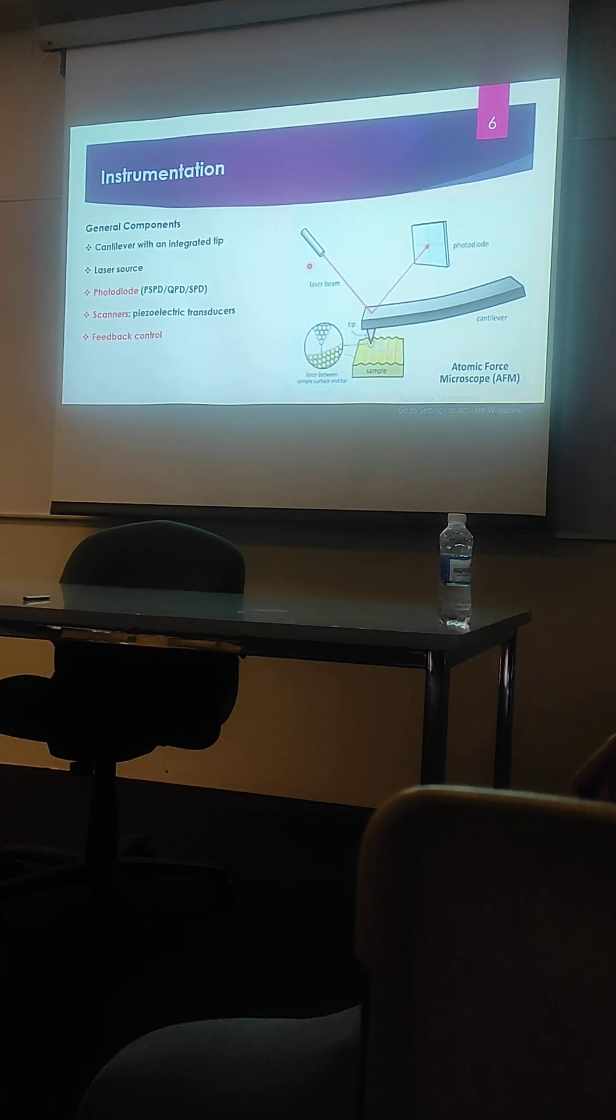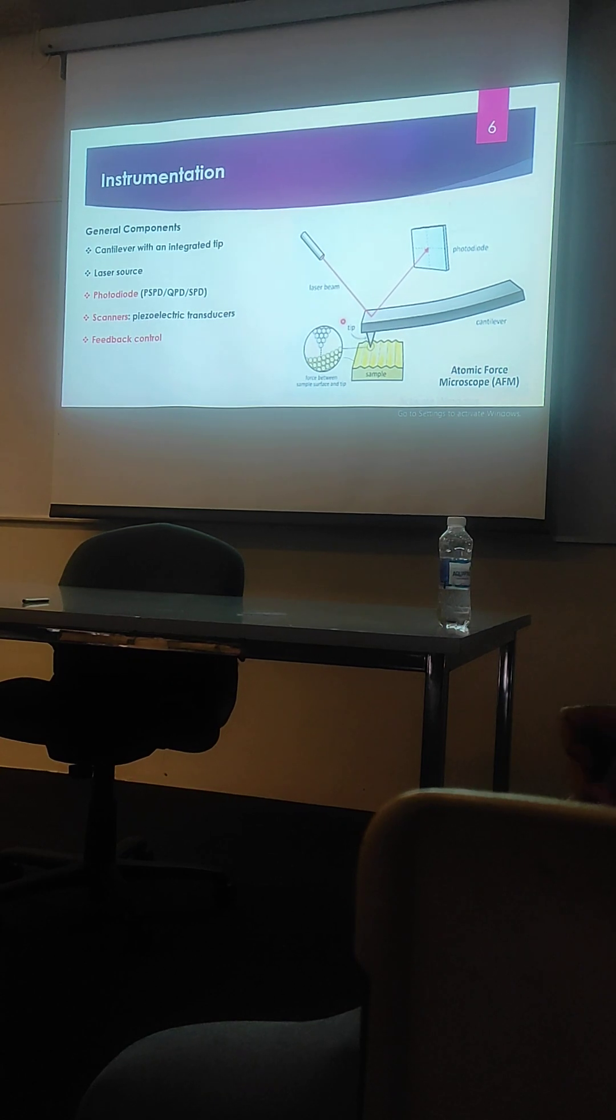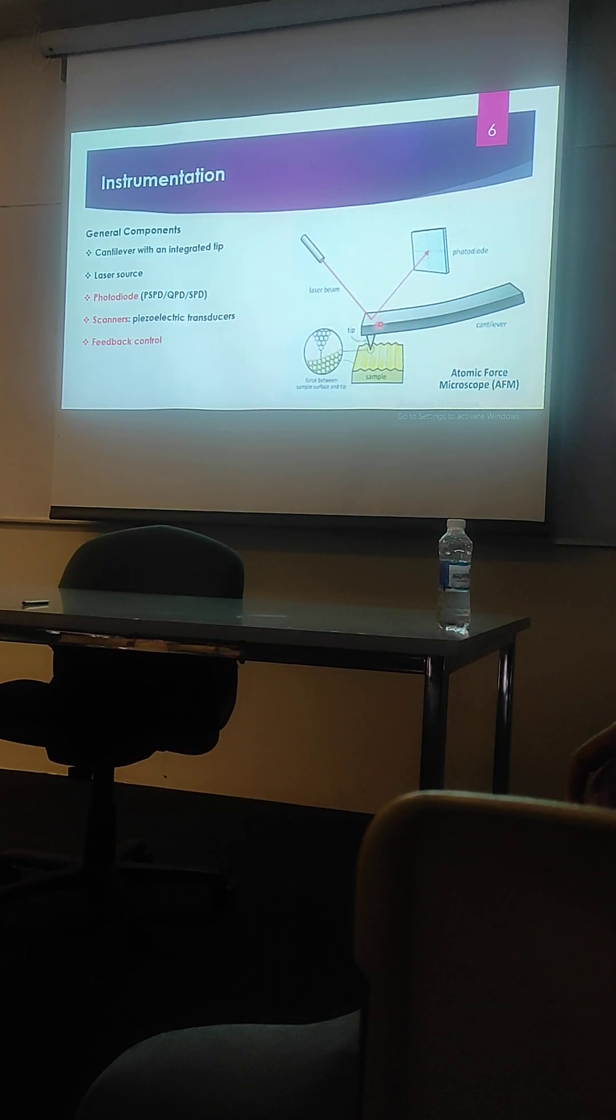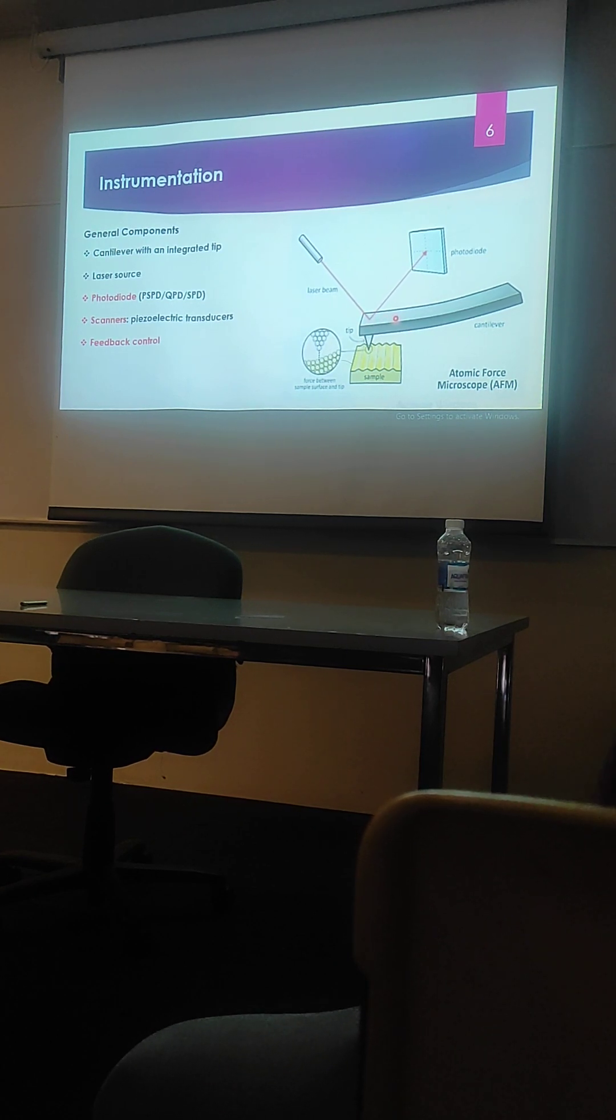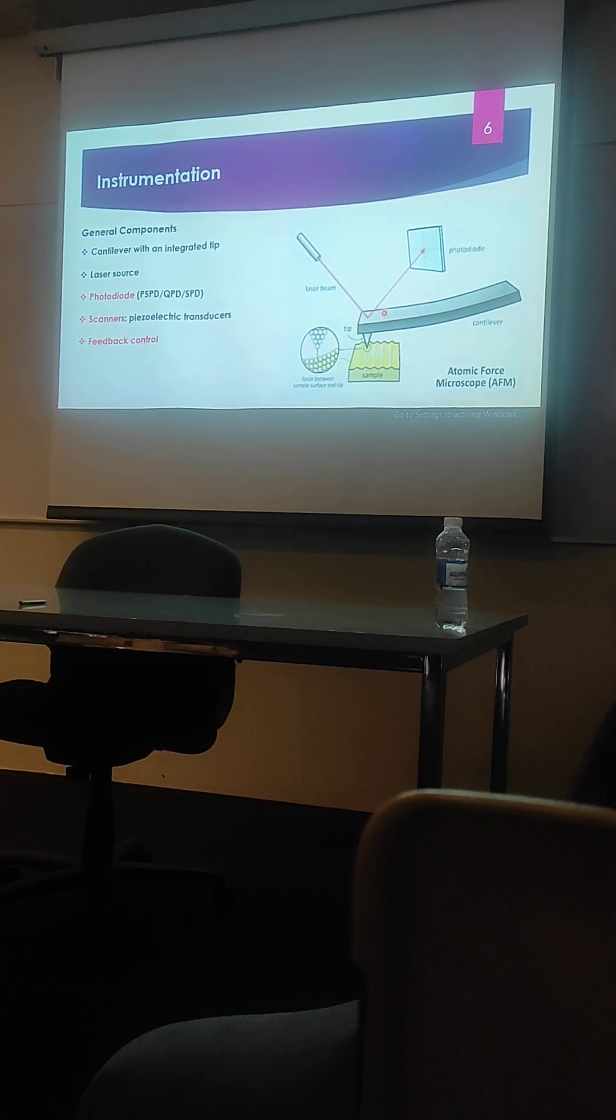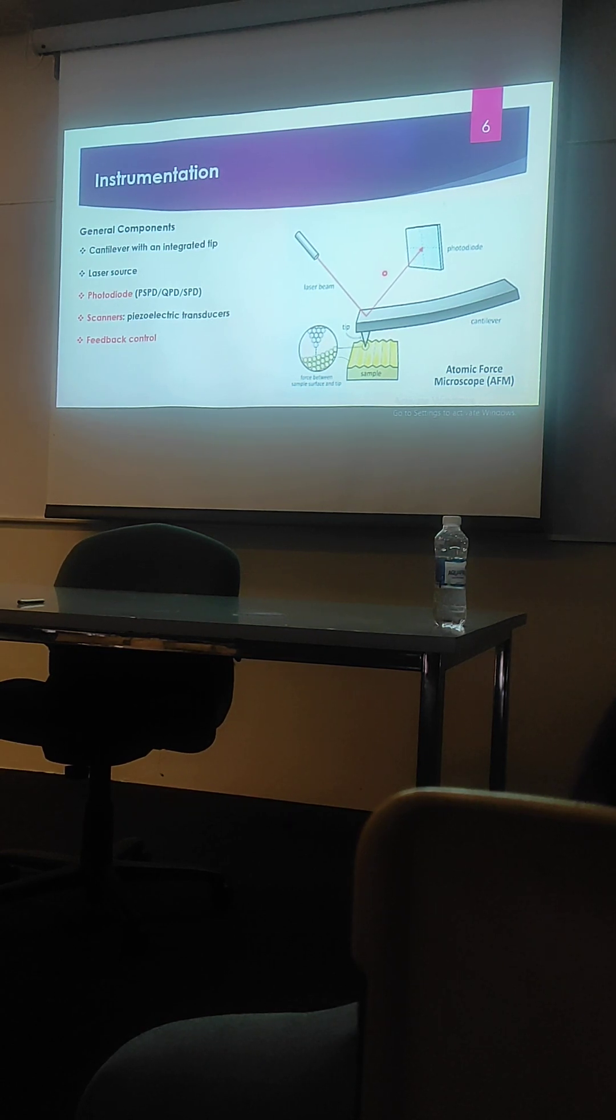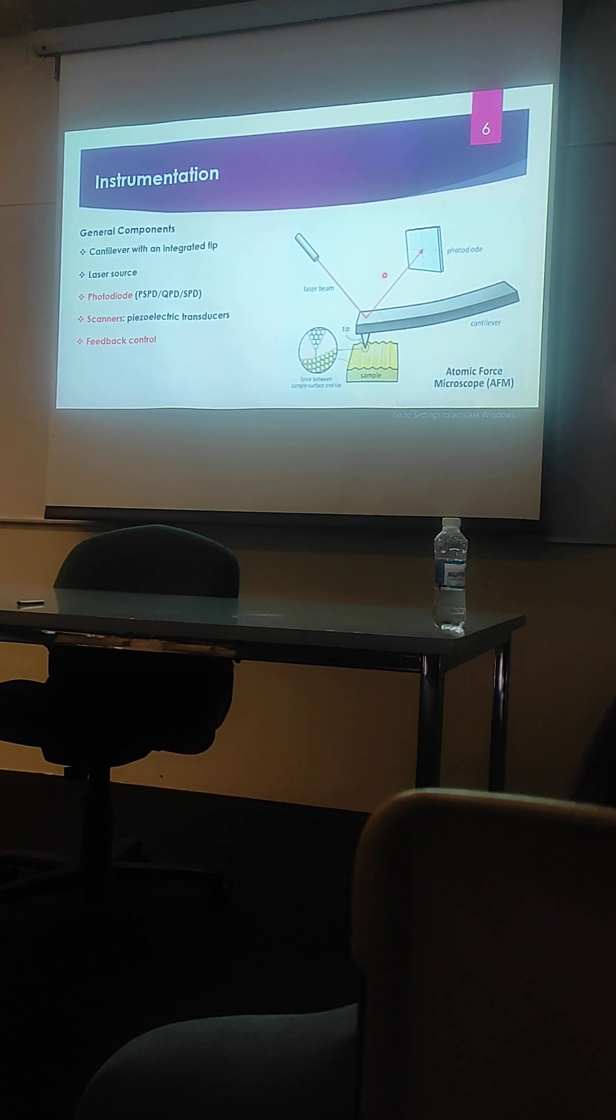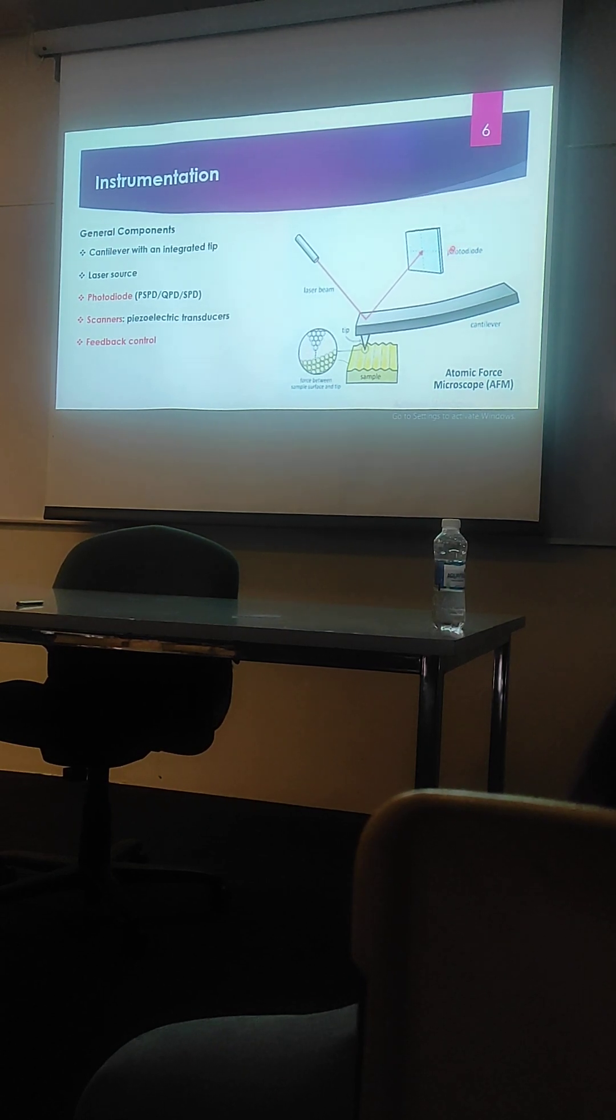We have a laser source. Here you can see this laser beam is incident on the front portion of this cantilever. It is usually painted with a metal surface so as to make it reflecting. And this light is then reflected onto a photodiode. We usually use the position sensitive photodiode, quadrantal photodiode or split photodiode for this purpose.